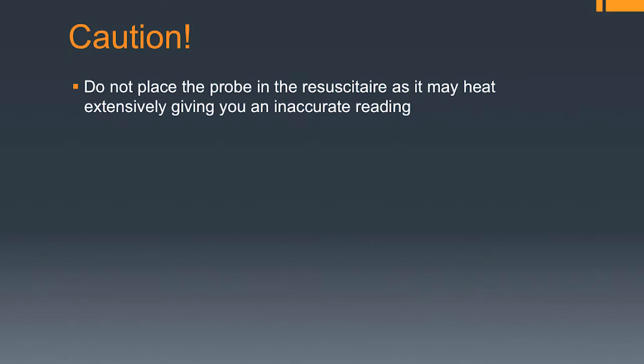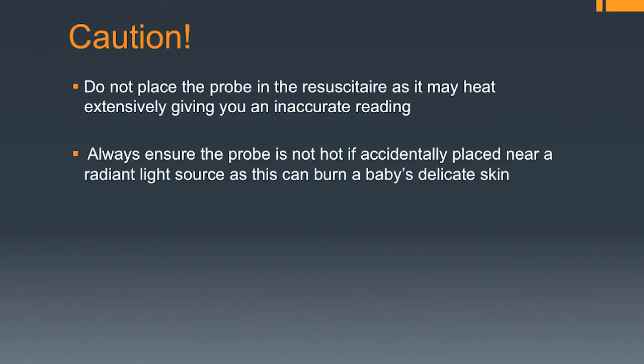There are some cautions that you should be aware of. Firstly, don't place the probe in the resuscitaire, as this may heat it extensively, giving you an inaccurate reading. Always ensure that the probe is not hot, and if accidentally placed in a radiant light source, wait for it to cool, as this can burn the baby's delicate skin.